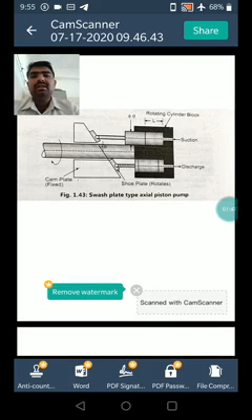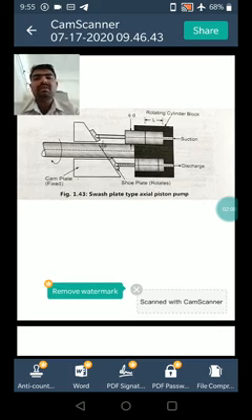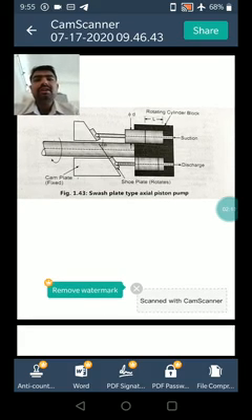A stationary plate has suction and discharge ports behind the rotating cylinder block. It admits fluid into those cylinders having a retracting piston and collects the discharge of the fluid from those cylinders having the piston moving rightwards. Now the flow rate varies directly with the driven speed of the shaft for a fixed angle of inclination of the swash plate with the vertical.